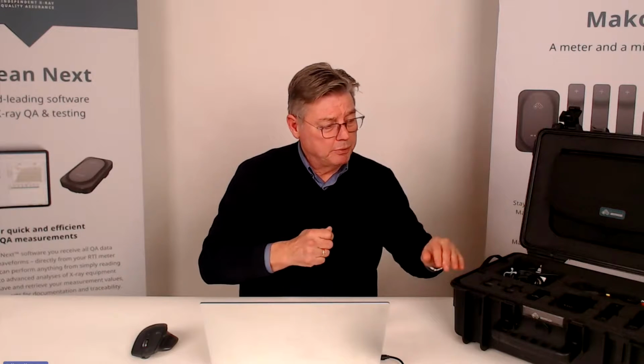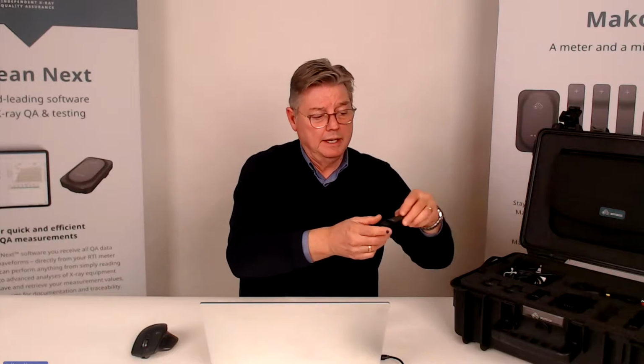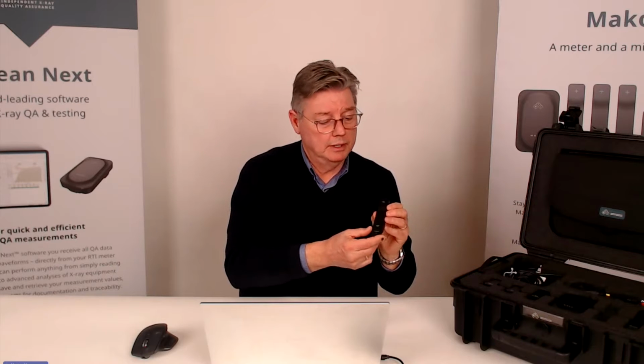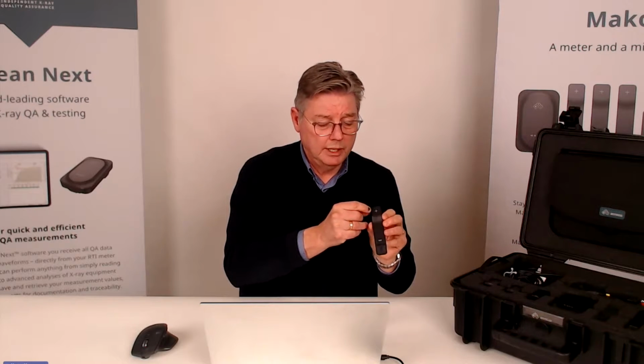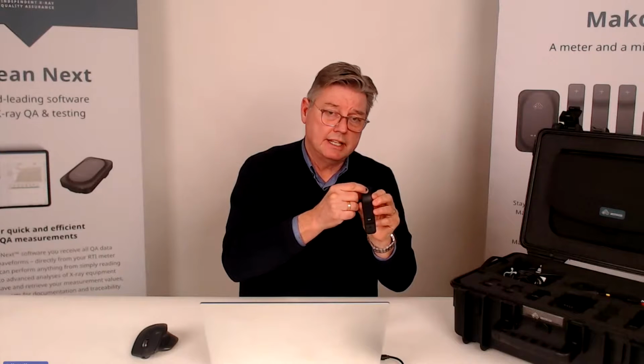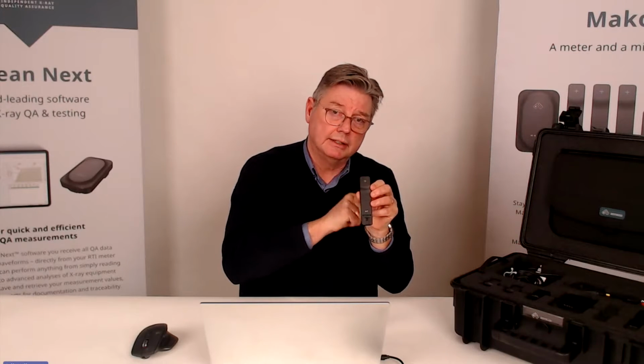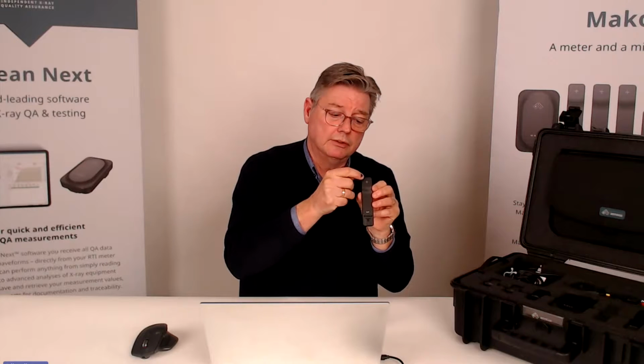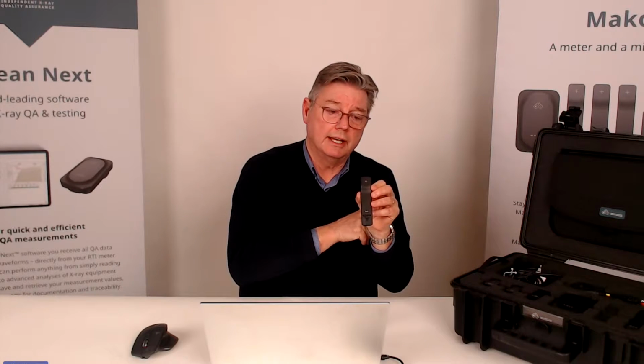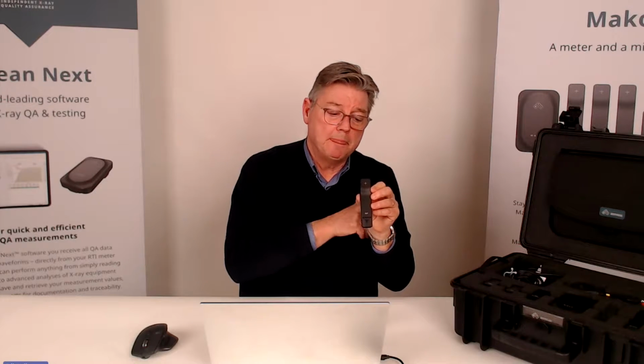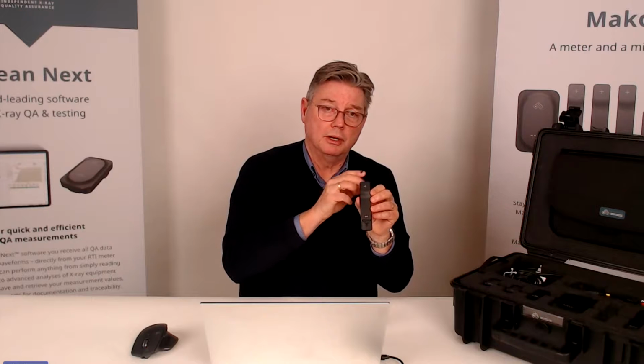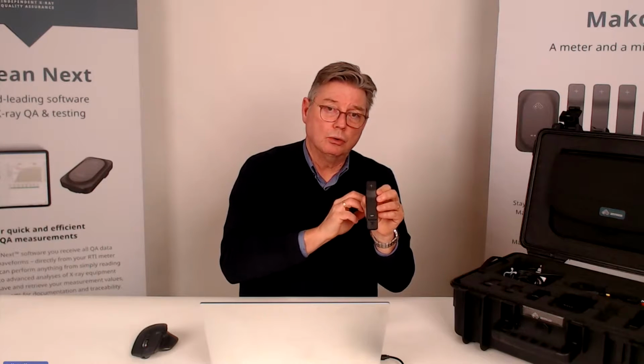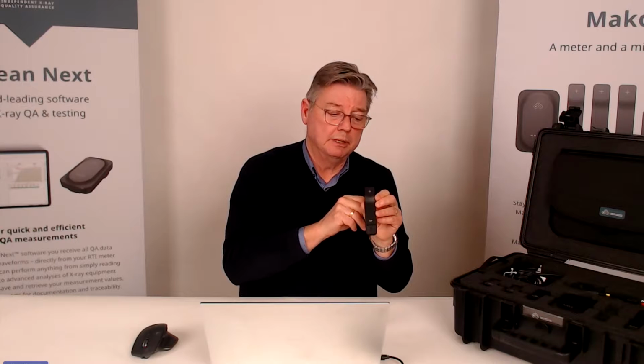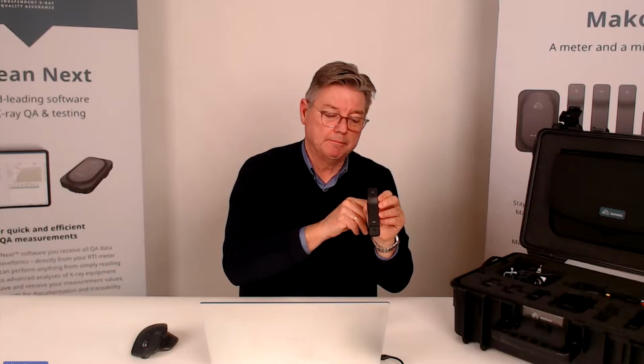Right, we talked about the probes. They have the same form factor. The active area is 7 by 7 millimeters, indicated by that crosshair right there. So that's the limits that indicate the size of the active area, 7 millimeters by 7 millimeters. There's also a backscatter protection collimation around it, making the total footprint 15 by 15 millimeters. That's the radiographic footprint, and we'll look at that a little bit later.